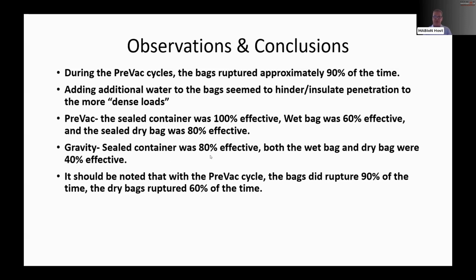The gravity sealed container was 80%. It failed on the tightly packed. Both the wet and dry bags were only 40%. 4 out of 10 were getting the kill. That's not good, especially when you know that your stuff has to come out. You have to get it dead coming out.